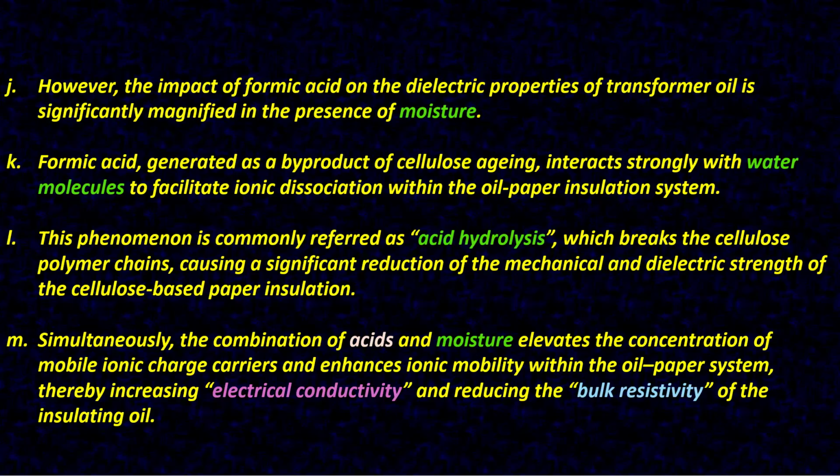Simultaneously, the combination of acids and moisture elevates the concentration of mobile ionic charge carriers and enhances ionic mobility within the oil paper system, thereby increasing electrical conductivity and reducing the bulk resistivity of the insulating oil.